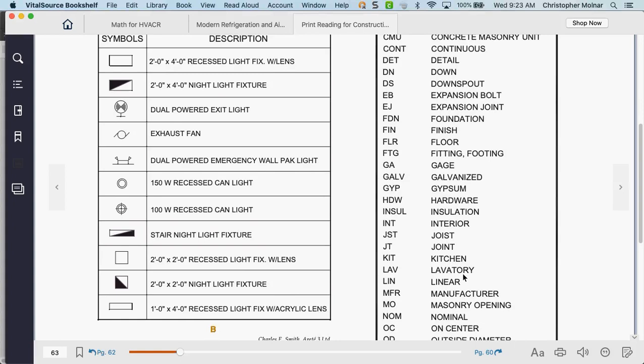What is special about kitchens and lavatories when talking about duct work? There's a specific type of duct work you do not put in either location: return ducts. I don't put return ducts in kitchens or lavatories — kitchens because of grease, lavatories because of the smells. I don't want that being sucked back into the system and redistributed through a building. So we never put return duct work in kitchens or lavatories — only supply duct work. With an exhaust fan, if air pressure gets too high, it forces itself out through the exhaust.